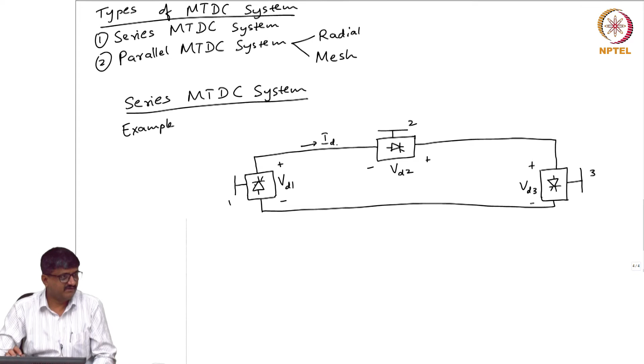So, if I try to operate a few as rectifier and a few as inverter, one of the converters is at least a rectifier, one of the converters is at least an inverter, then the polarity of the voltage across the DC side terminals is dependent on whether it is rectifier operation or inverter operation. See the polarity, suppose I take the polarity of this with respect to this, the polarity of this with respect to this, polarity of this with respect to this. Suppose I call this VD1, VD2, VD3 and the current is say ID. Now, at least one of these VD1, VD2, VD3 should be positive and at least one of these should be negative. If it is positive, it is rectifier, it is negative means it is inverter.